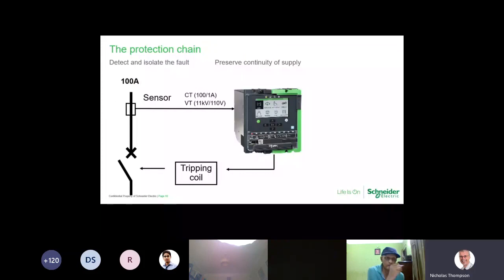We've got our protection relay, we've got a sensor, we've got a trip coil, and we've got a circuit breaker. So I always describe the circuit breaker as being the brawn and the protection relay as being the brain. As I've described earlier, the sensor is the link between the primary circuit. It's not directly connected to that circuit, and it's part of the chain. I always refer to it as the protection chain.